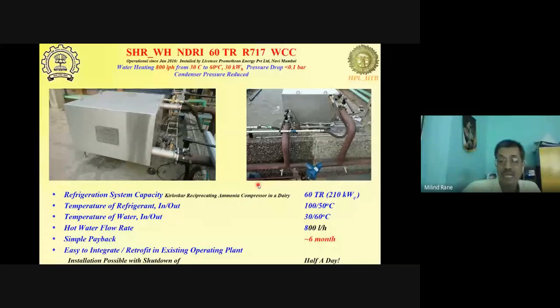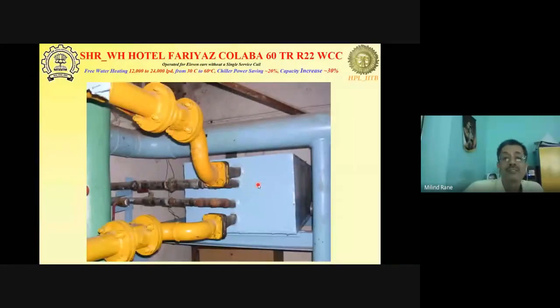This was a hotel unit, which was installed on a 9-year-old chiller. When this got integrated, it increased the cooling capacity of that chiller by 30%. And they continue to operate the chiller up to 20 years total life, that is 11 more years after we integrated this. The power saving was around 20% because that was an old chiller. The saving was very significant. And this was in addition to the hot water being produced, 12 to 24,000 liters of hot water from 30 to 60 degrees centigrade.